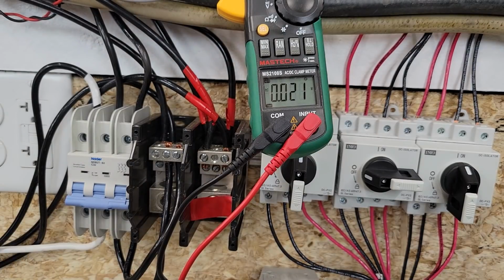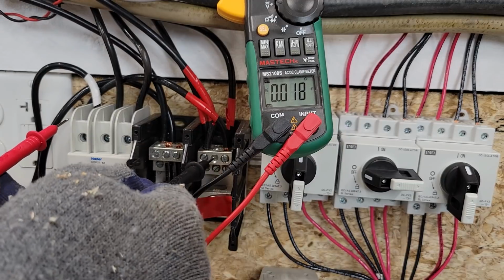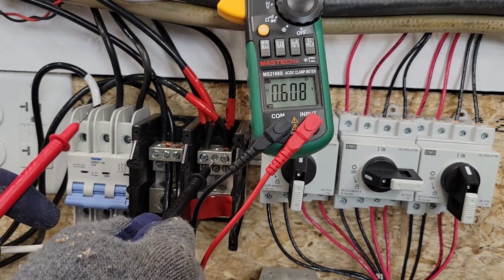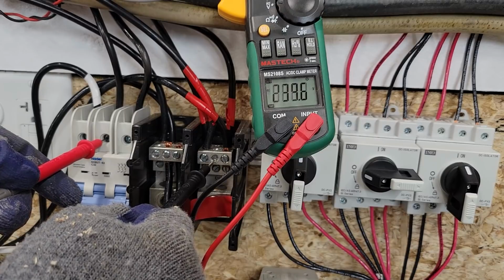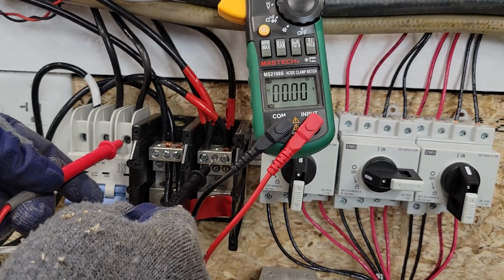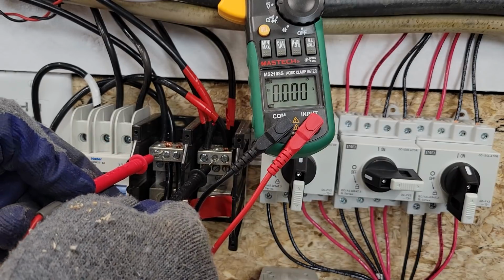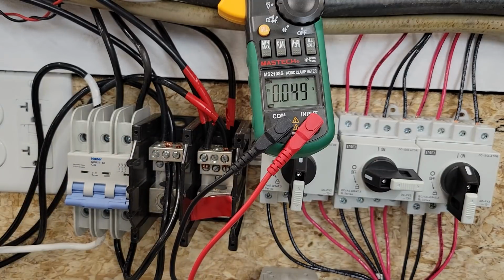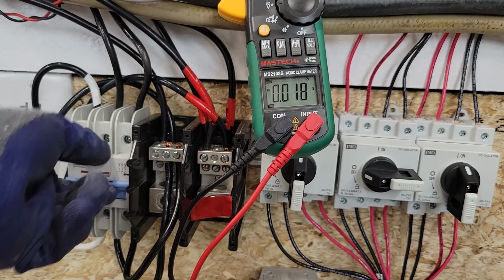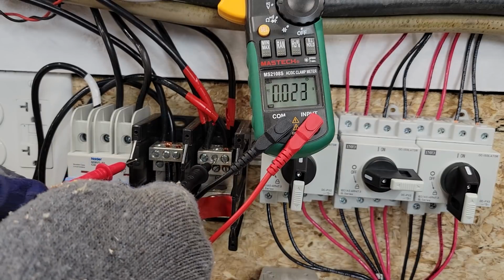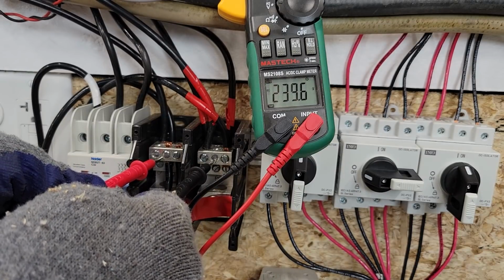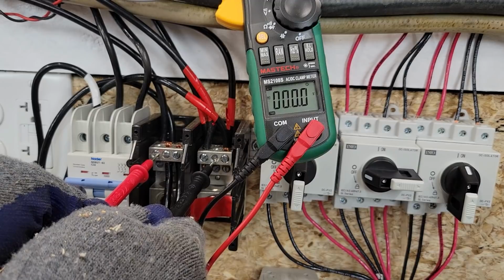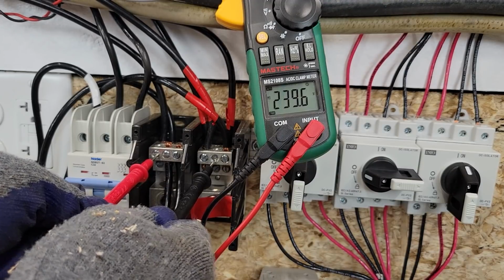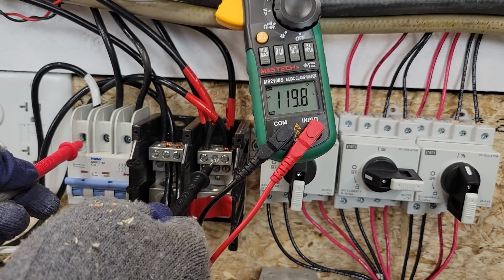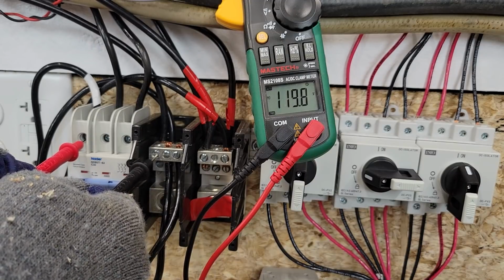Okay, I think all the wiring is done and both inverters are on. So let's check our voltage. So going from this one, which is the common, we're going to check to inverter 1 is 240 volts and 240 and nothing right here because we don't have the circuit breaker on. Now we'll try turning the circuit breaker on. And now we should have 240 volts here. And we do. We have 240 volts. So now that we have 240 volts here, let's check to, yep, 120. And over here is also 120.